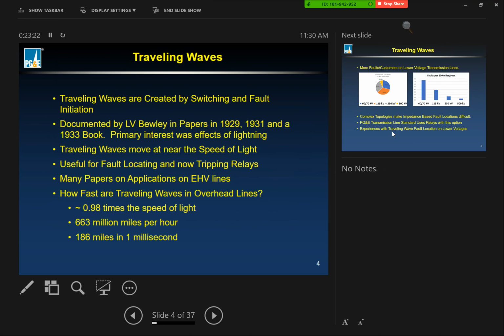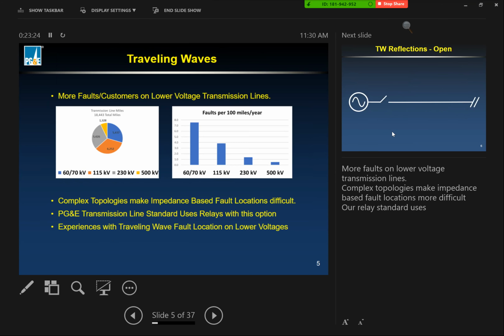So they are not nearly as accurate to do conventional fault location, which is impedance-based methods. Basically we're recording the I and the V. We know the phase conductor is a certain ohms per mile, and so we use that basic function with some complex add-ons to reduce error to determine typical fault locations.